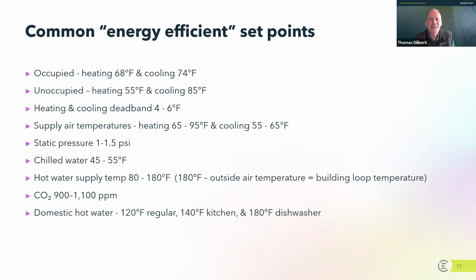So I wanted to give you a list here on this next screen of what I'm calling the most common energy efficient set points. Would all of these fit in every circumstance? No. But I just wanted to draw your attention to some of these numbers. And as you review these screens that we're about to go through, I want to make sure these are the numbers that you begin to lock in on. So the occupied set points for heating and cooling, we mentioned those already, 68, 74. Unoccupied, 55 and 85.